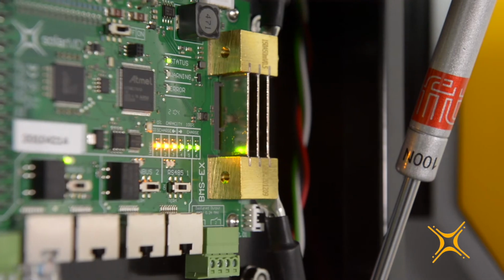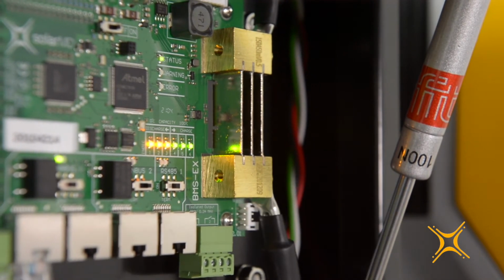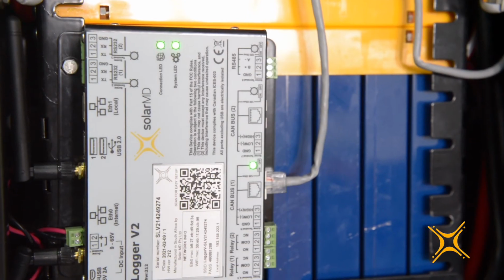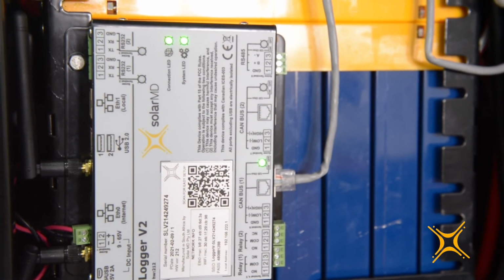BMS EX is fitted with a 150 amp calibrated shunt. The shunt offers very accurate current measuring with a resolution of 10 milliamps, measuring every 143 milliseconds. The measurements are tracked over time by the BMS and we are able to accurately determine the battery state of charge. BMS EX is the only management system in the market that can be remotely updated through the revolutionary Logger V2. The BMS is equipped with 3 communication interfaces hosted over 5 connection ports.